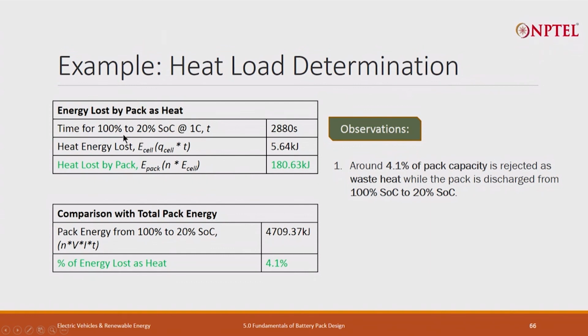When your SOC is 100, when you bring down the SOC from 100% to 20% at 1C rate, what are the things we have to do? When I say 1C rate, it was 14 ampere. If I reduce the C rate, let us suppose to 0.5C, what would be the current? 7 ampere. And if the 7 ampere current is there, then my heat energy lost would be 1 by 4 times.